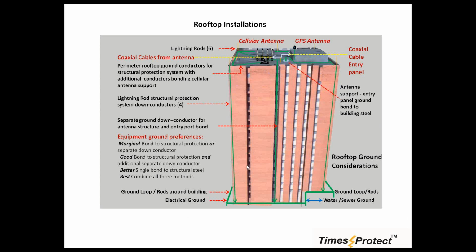There was also a question about, hey, can I use the cold water pipe? Well, yeah, if you are certain that there are no plastic pieces interconnecting some of the copper, or if you are sure that plastic pieces won't be added down the line due to modification of the cold water pipes and so on. It is always good to have redundancy. Cold water pipe is good, as long as you have a total metallic cold water pipe and you are pretty sure that it is in very conductive surroundings. But in addition to this, I would advise running an additional redundant ground system, just in case somebody has to cut a piece of broken metal pipe and fit it with PVC.